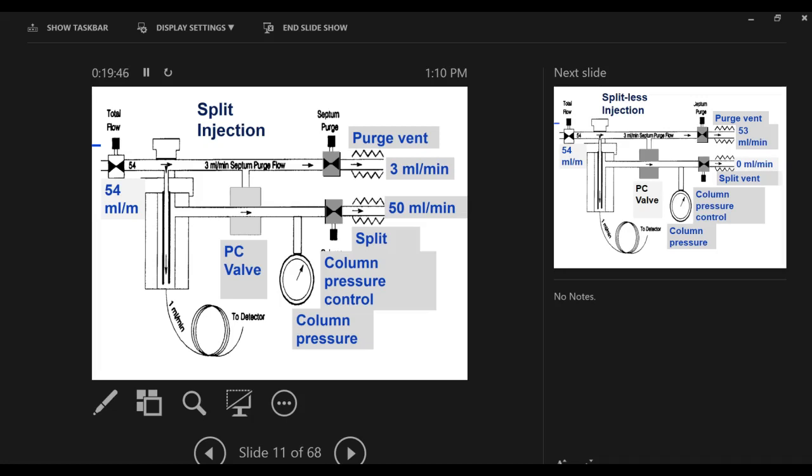Well, this is 250 degrees centigrade. That's a rubber septum, and that rubber septum's going to degrade. It's going to be giving off volatile compounds. And as this gives off volatile compounds because of its degradation, they can either go this way and screw up all your analytical work, or you can just flush them out here. So the volatiles from the rubber septum will come down and they'll go that way. Because you're going to inject your sample down here. So you inject it outside of this flow, and that just keeps things clean.